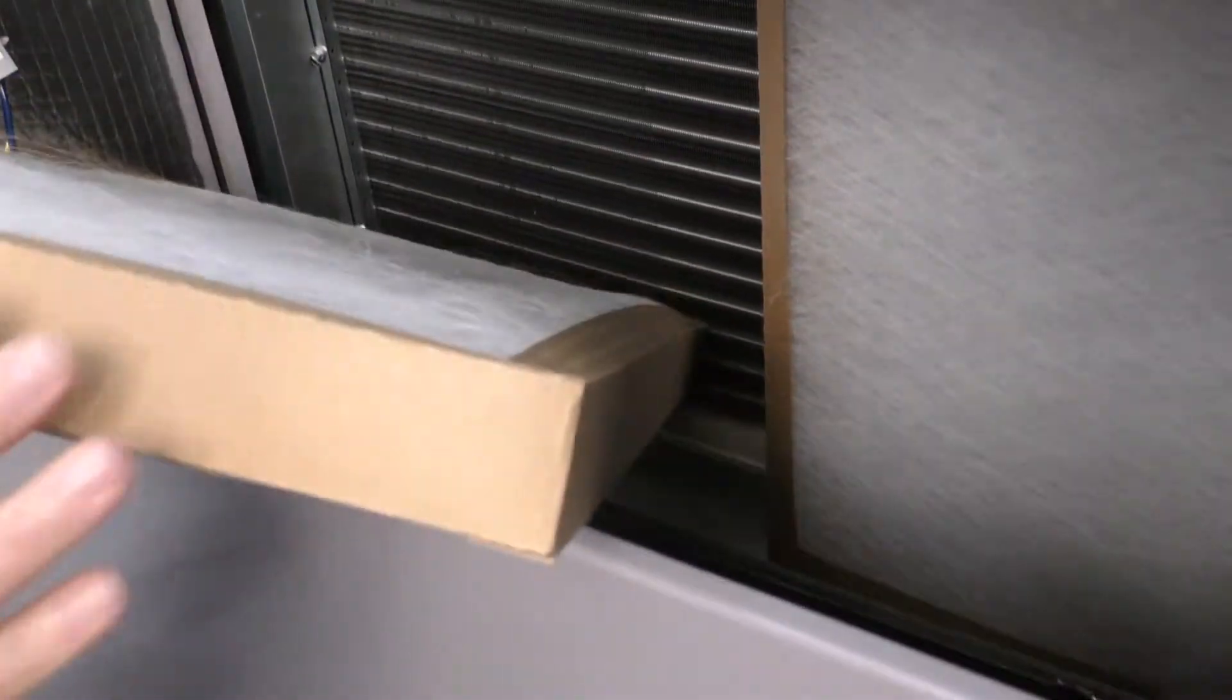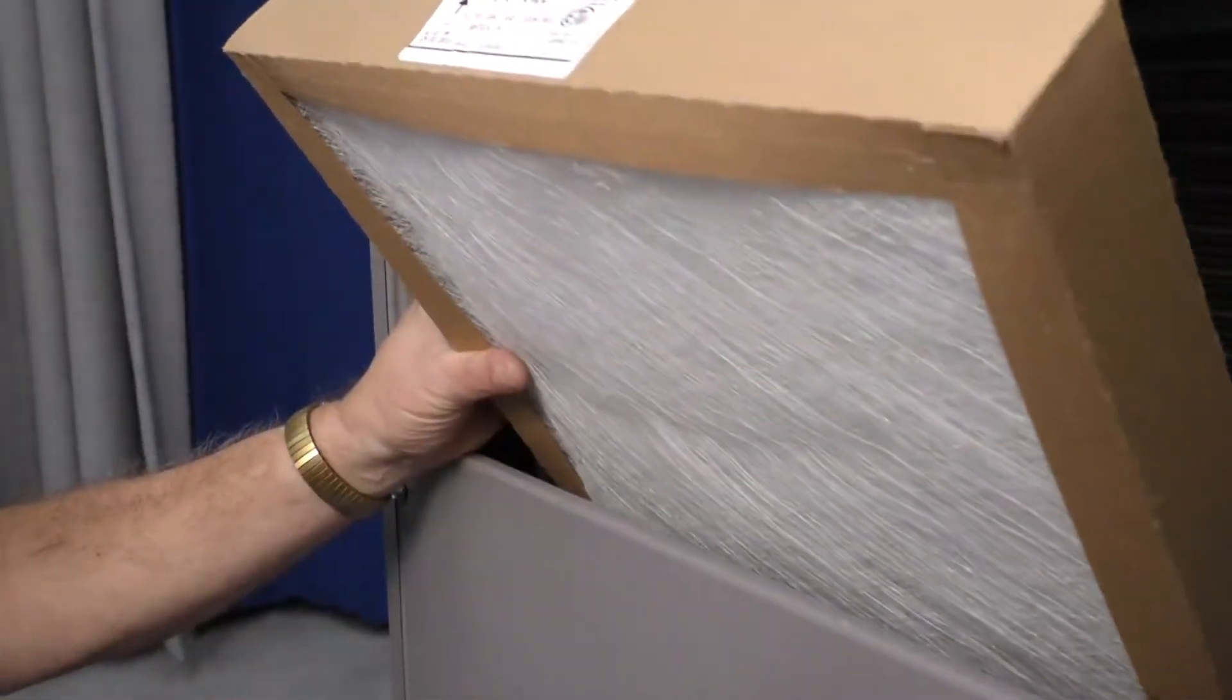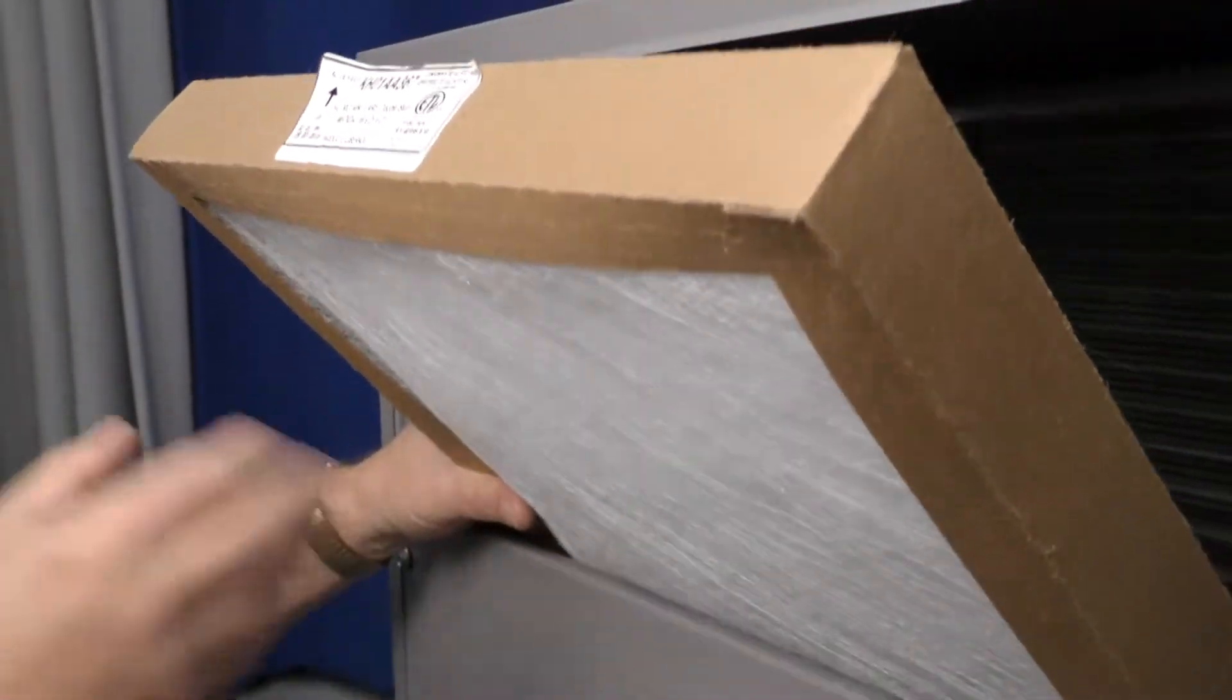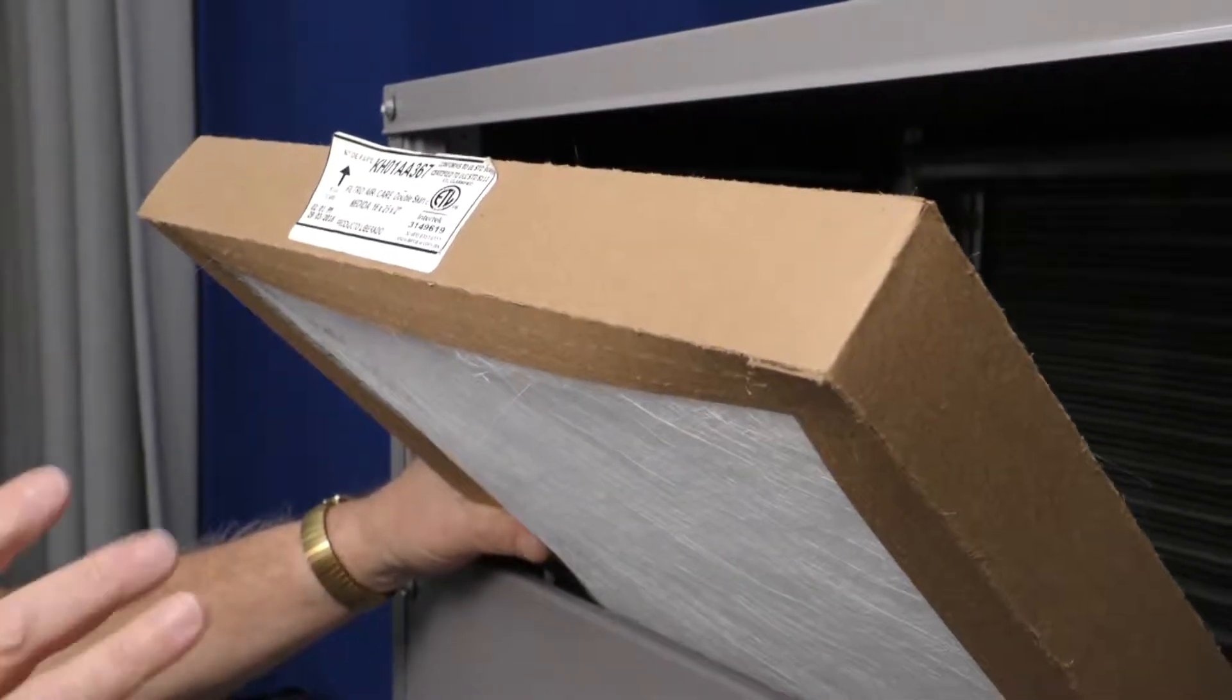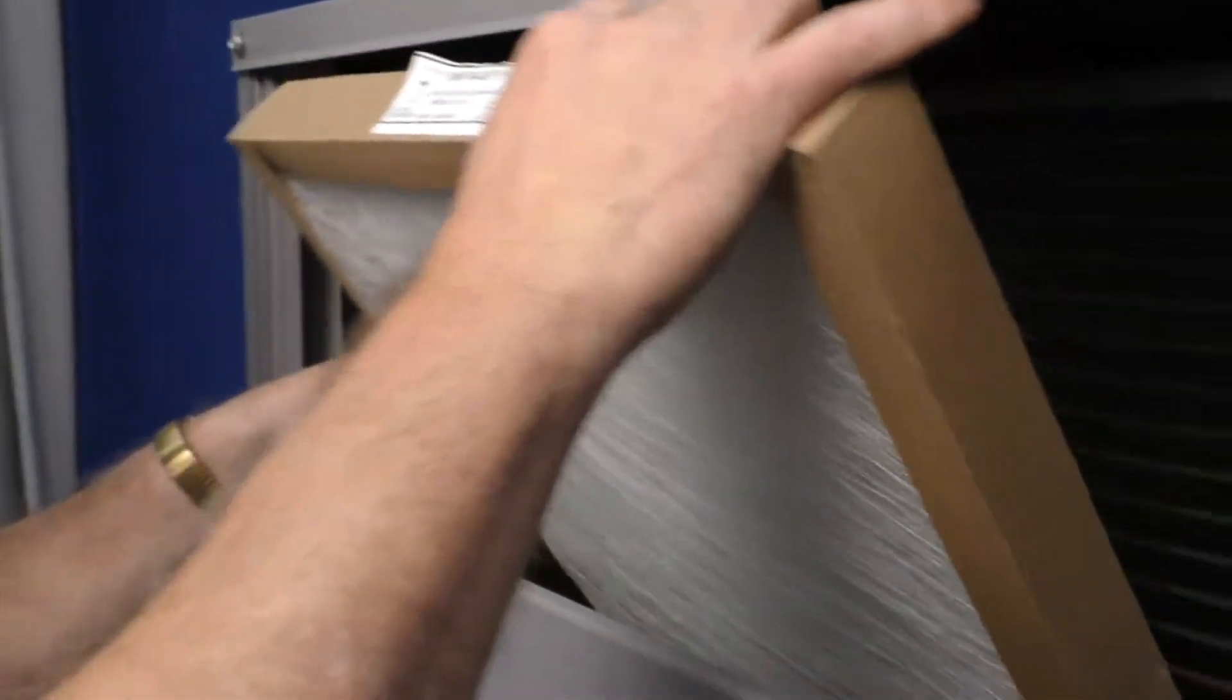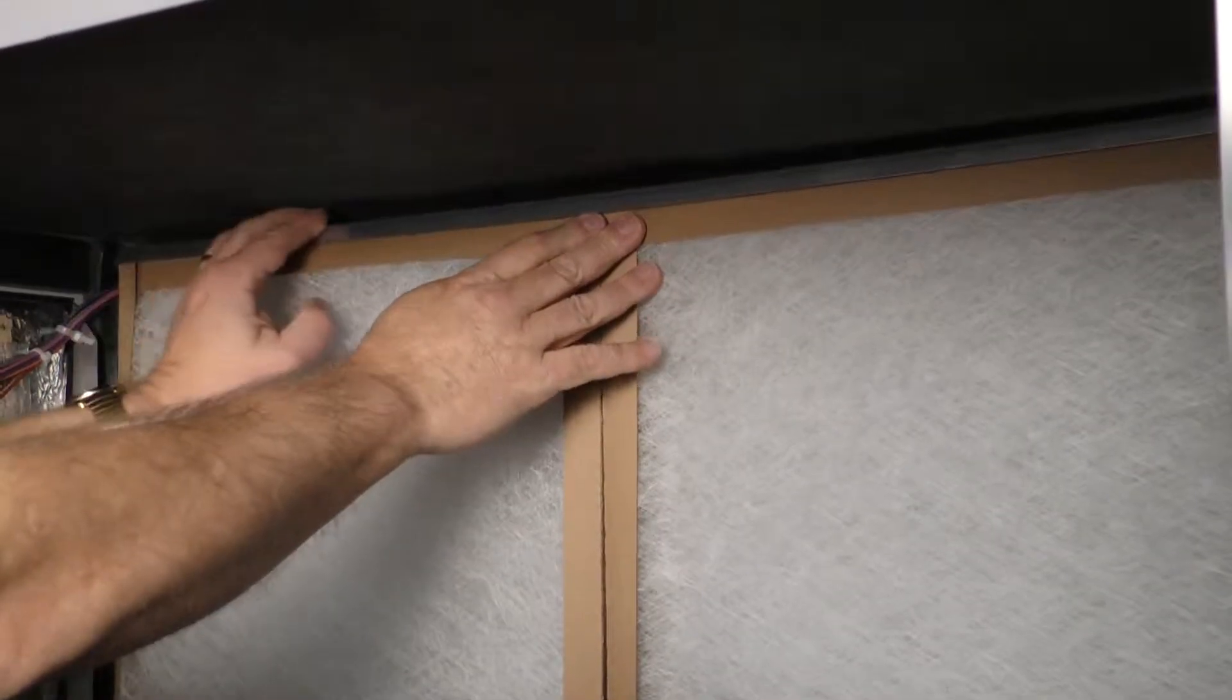Pay attention to the directional arrow on the filter as there is a coating on the entering air side and the leaving air side that allows it to trap dust and prevent the fiberglass fibers in this particular case from being entrained onto the coil and into the space. Make sure that you pivot the upper rail down, which holds the filters in place.